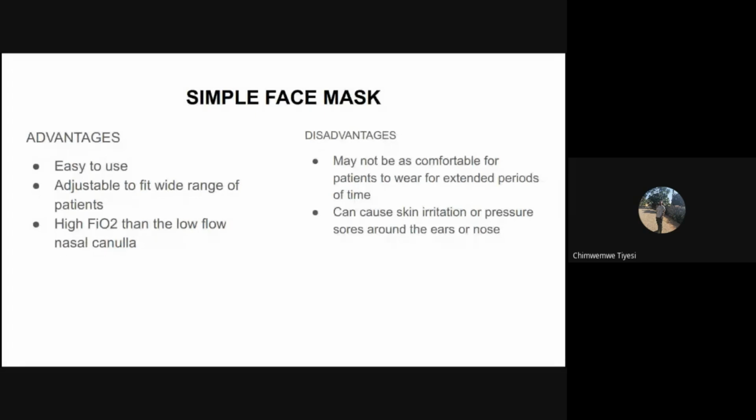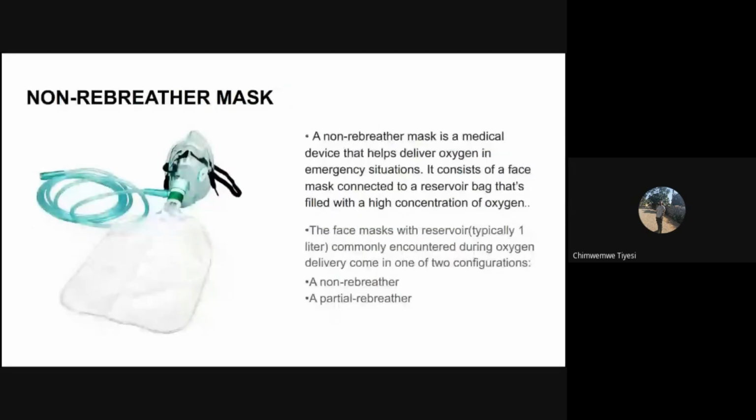So thank you, Emmanuel. I will now talk about non-rebreather masks. A non-rebreather mask is a medical device that helps deliver oxygen in emergency situations. It consists of a face mask connected to a reservoir bag that's filled with highly concentrated oxygen. As you can see in the graphics to the left, you have the bag, which is usually around 1 liter, the face mask, and also tubing that goes to the oxygen supply, either a concentrator, oxygen tank, or cylinder, or the main pipeline from a PSA plant.